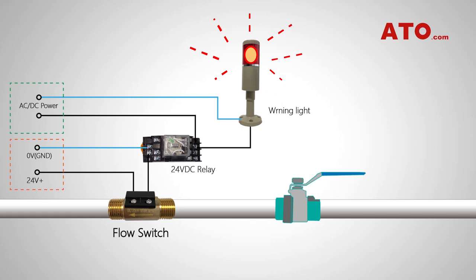The working principle is explained as follows. The water flowing through the plastic valve core enables the onboard permanent magnet to approach the transducer on the external black switch for sending signals. When there is no water flow or obstruction, the two magnets inside produce a repulsive force to reset the switch. Simply put, signal output depends on whether there is water flow.